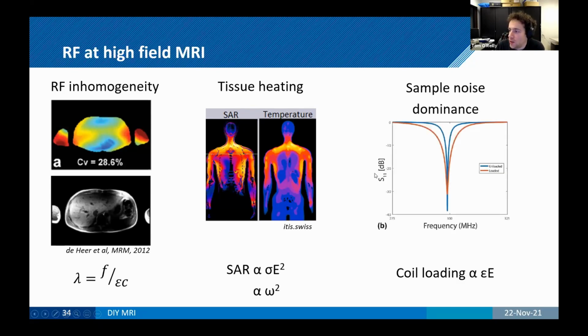And then this is not per se a disadvantage, but it's just a general practical thing, which is that at high field, you're completely sample noise dominated. So when you put the antenna near the body, the electric field is going to interact with the conductivity inside the body. I'm pretty sure that should be a sigma. And that basically adds a giant resistor to your coil. So it doesn't really matter how well you build your coil, because the losses caused by the interaction of the coil with the body are going to dominate any losses that you're going to have inside of your coil.